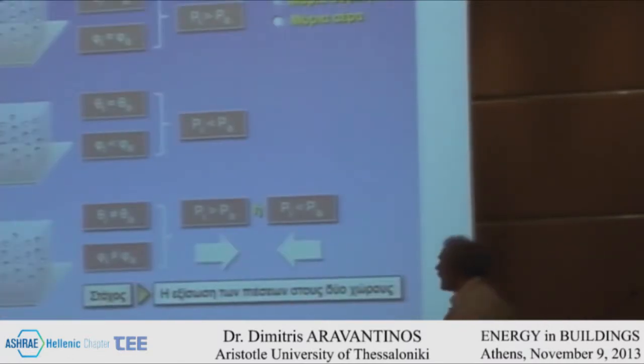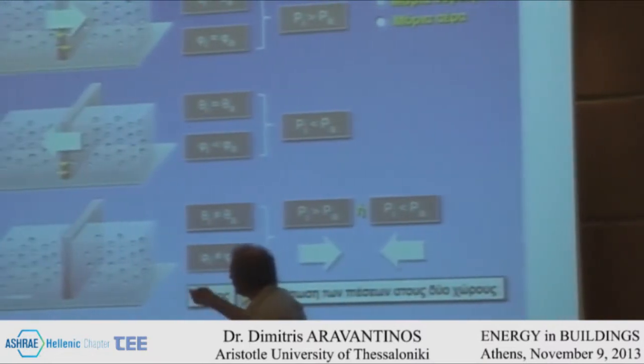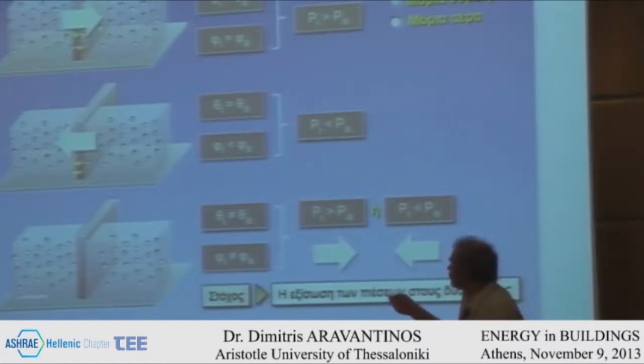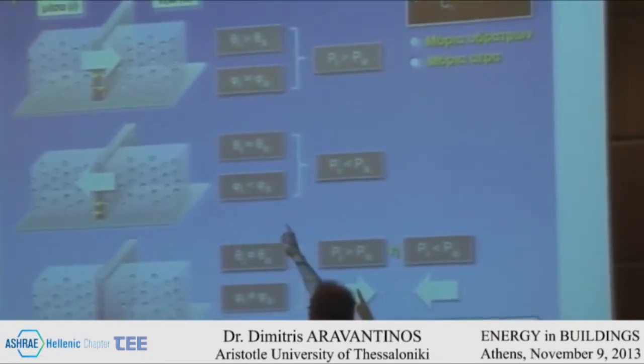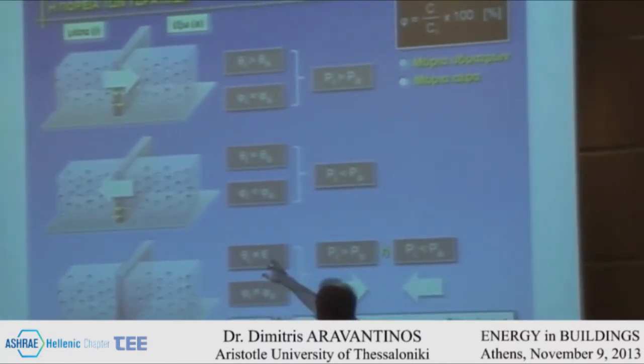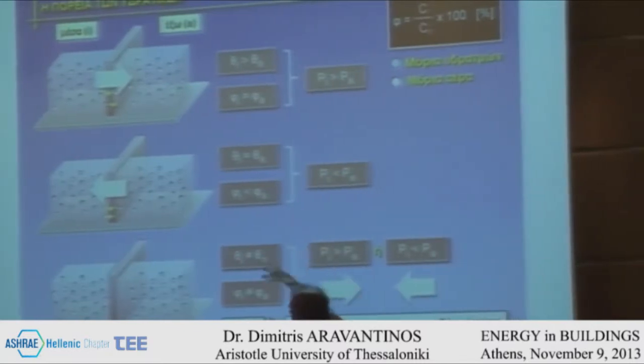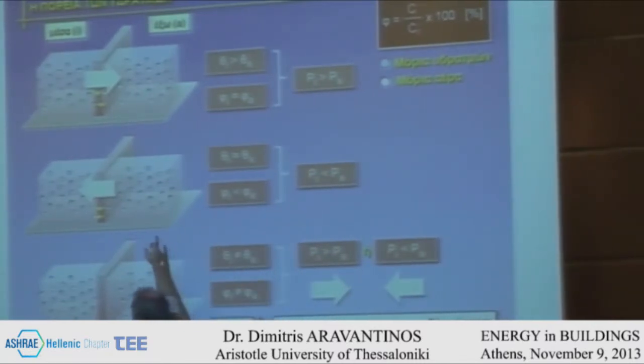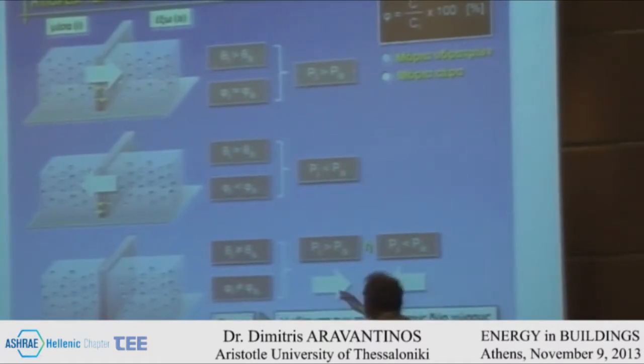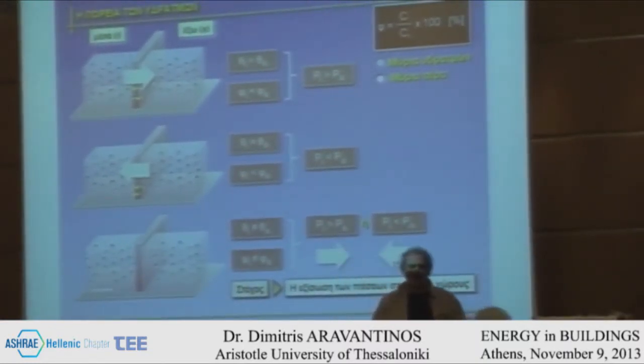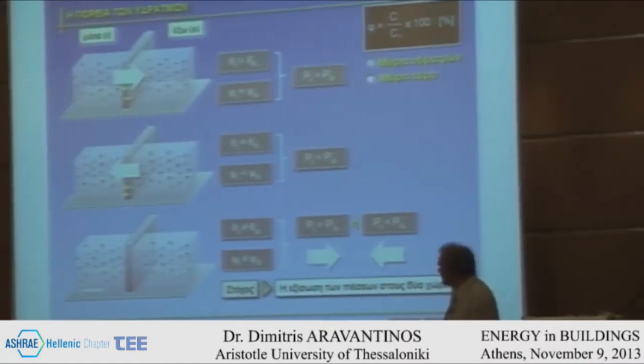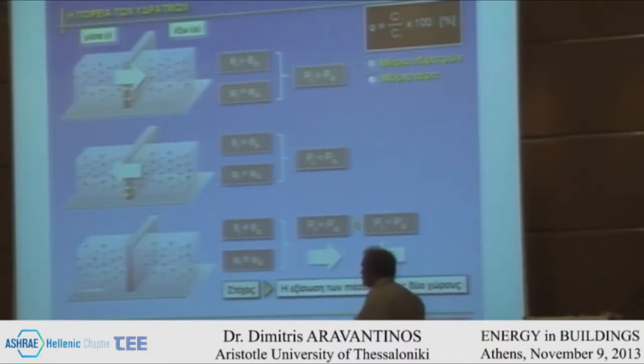The direction of vapor flow will always depend on the temperature on both sides and the relative moisture. If the temperature on one side is higher and the relative moisture is the same, it is easy to see where the vapor will go. If temperature is the same on both sides, the difference in relative moisture decides which way it moves. But there is always a problem when there are discrepancies between the two, because in that case we cannot decide right away where the vapors will go. This is where we need to take vapor pressure into account.